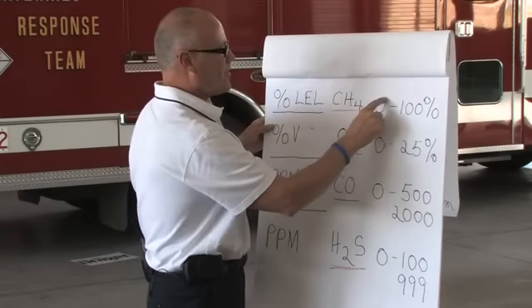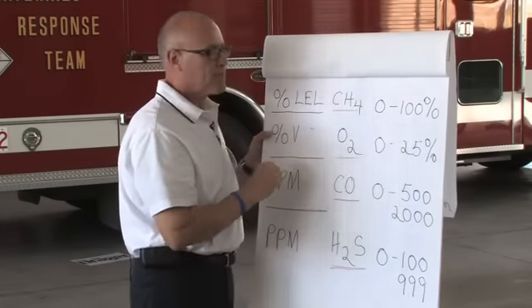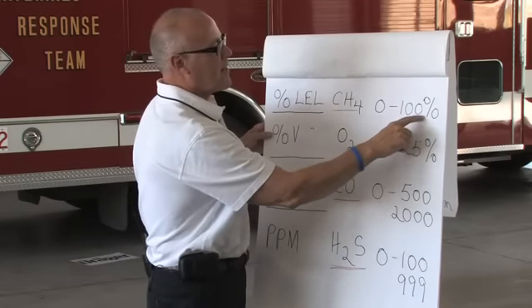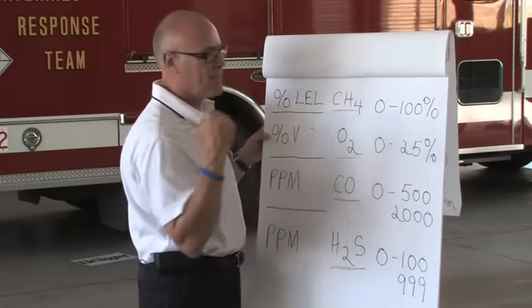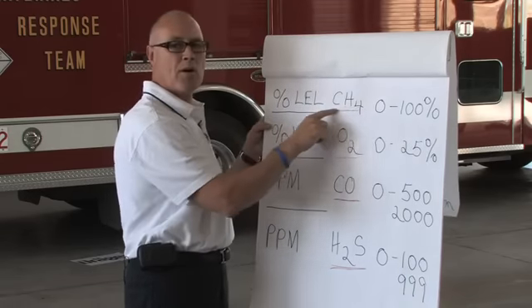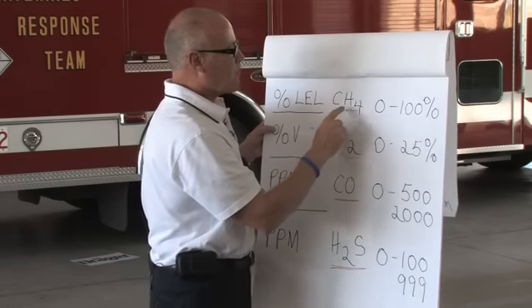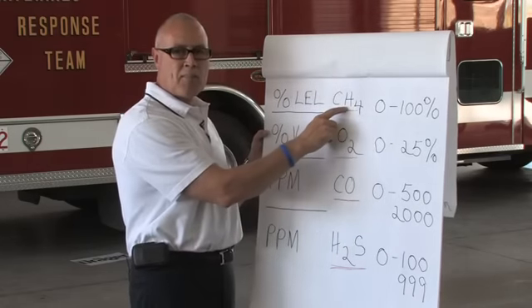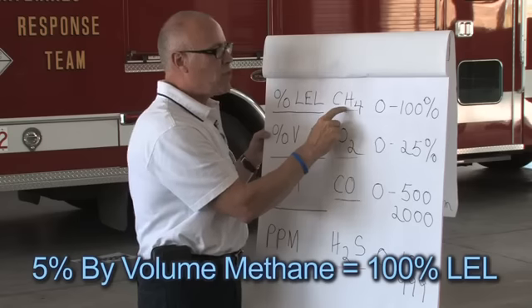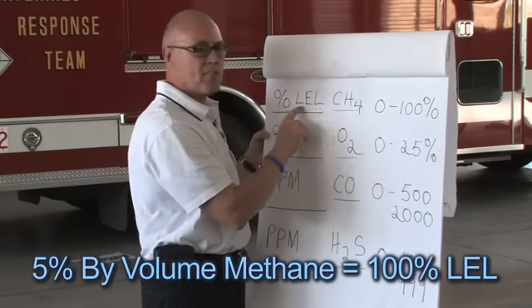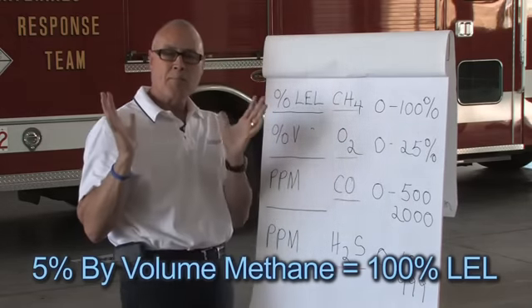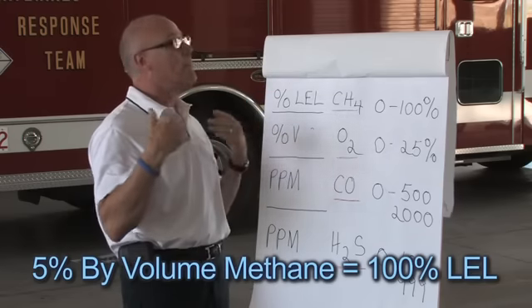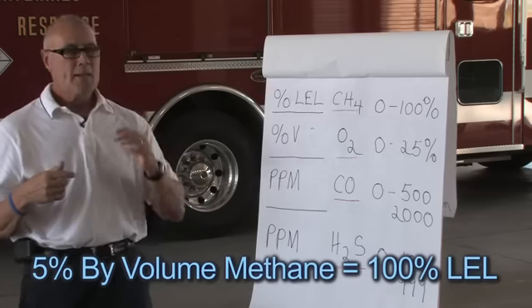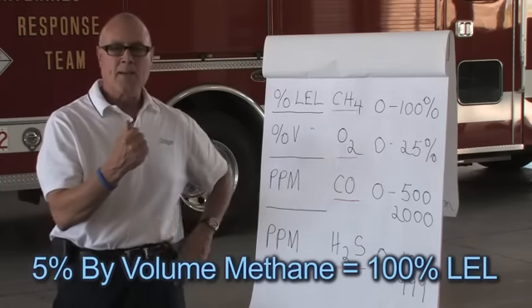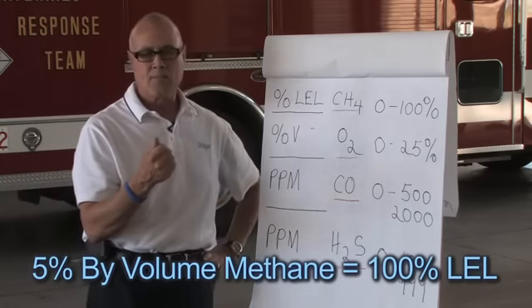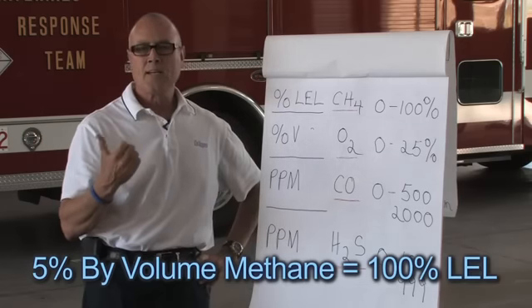So 0 means you have no gas, no vapor. But once you get to 100% of the lower explosive level on these instruments when they're calibrated to CH4, what that means is that if you get up to 5% by volume methane, that equals 100% of the lower explosive level. So 5% by volume methane in this room, mix it up, lots of convection. I can technically get a heat source of 999 degrees with the right amount of air to create an explosion.